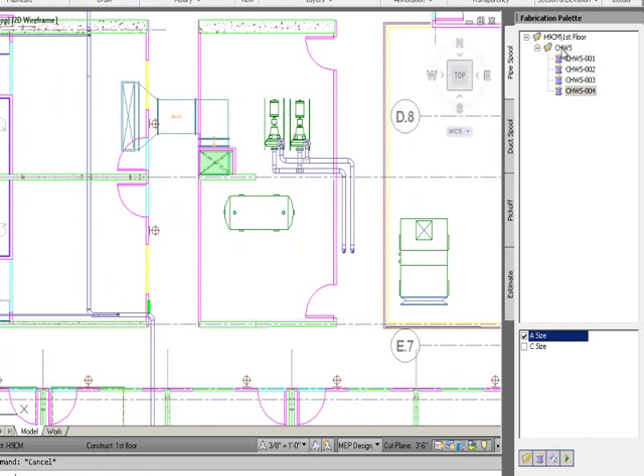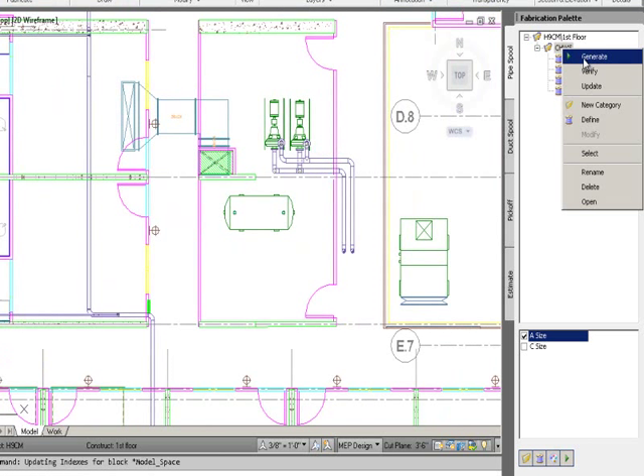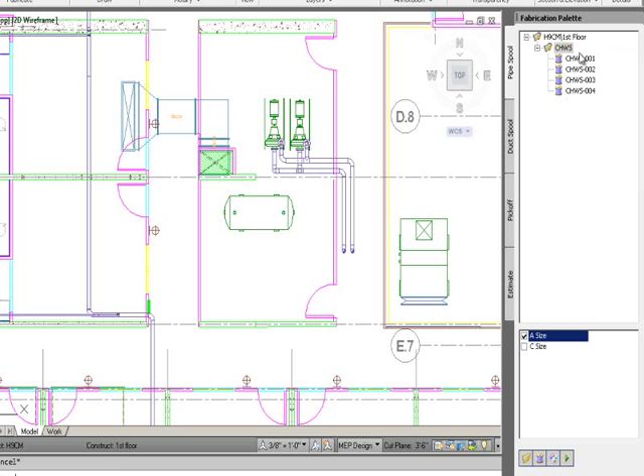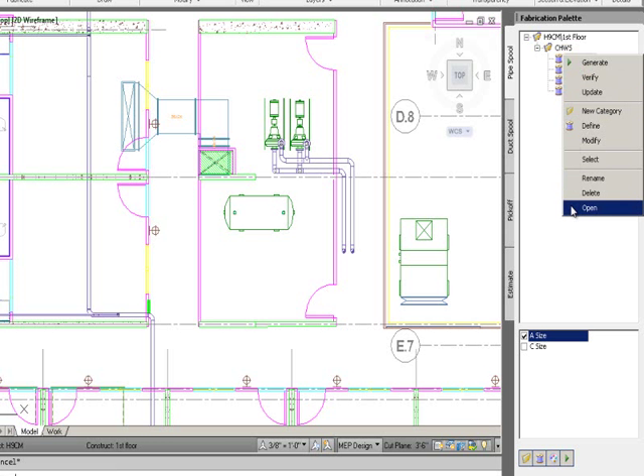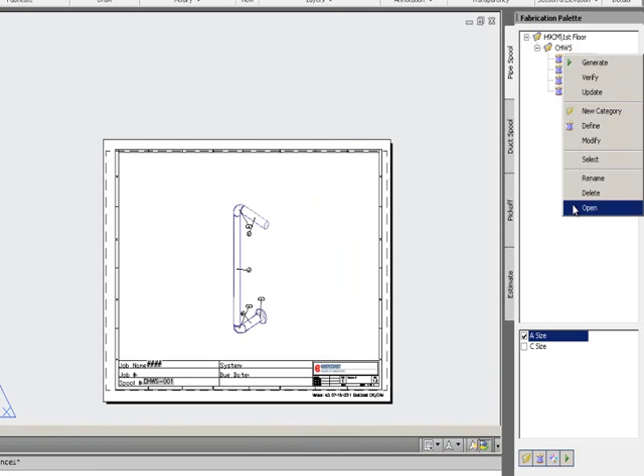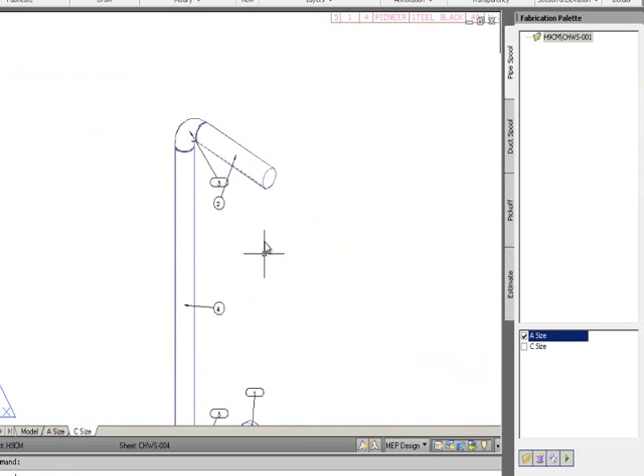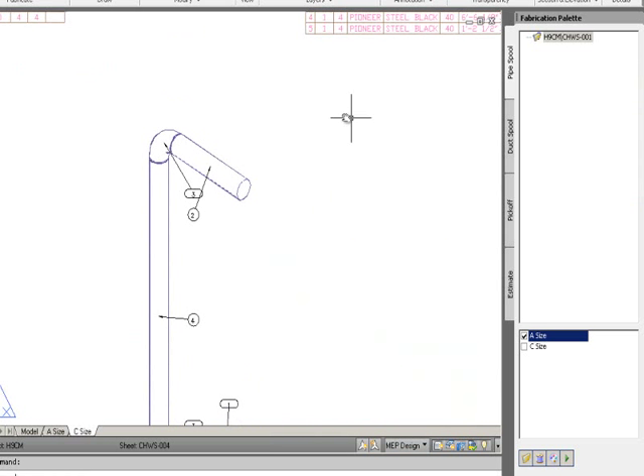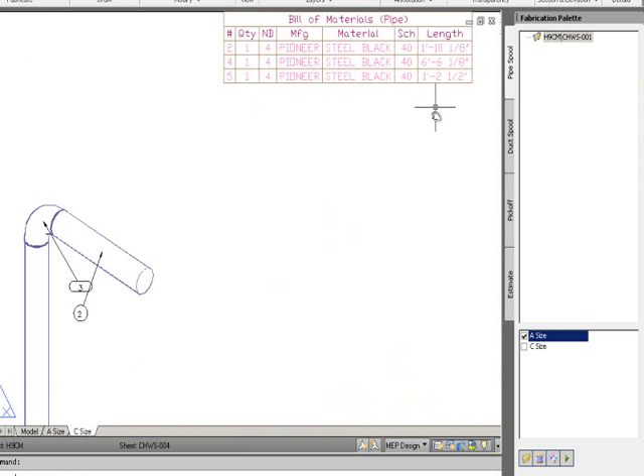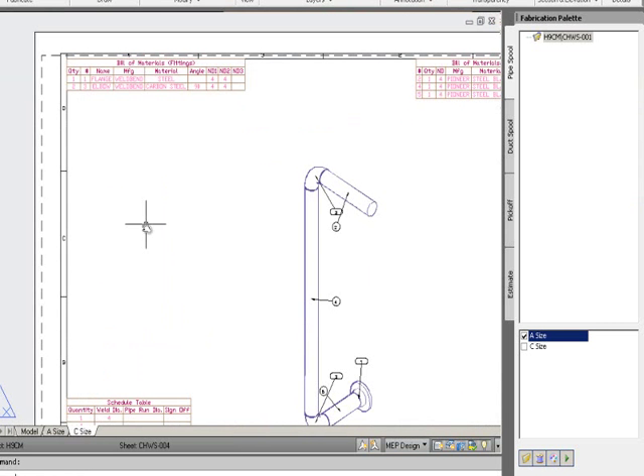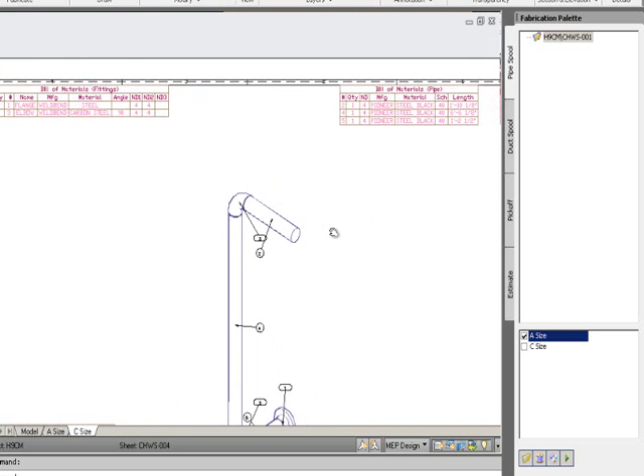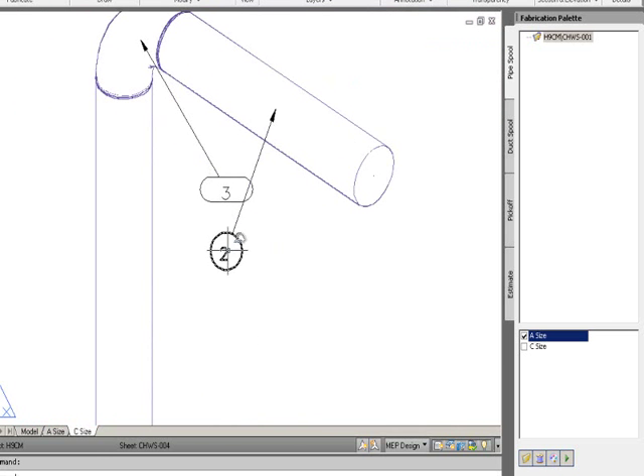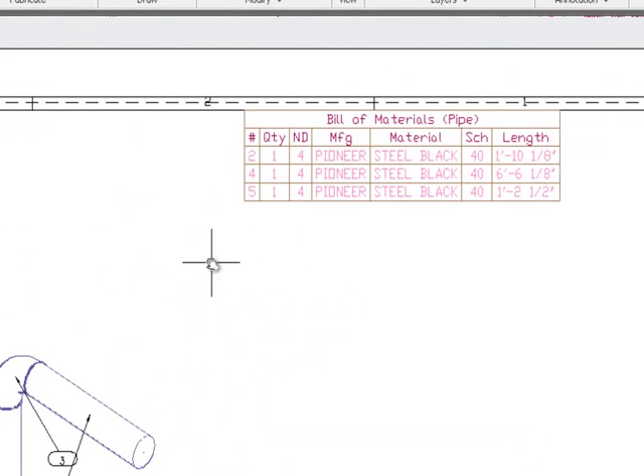From there I generate those four spools, letting the system create a spool drawing for each one. Opening the first spool, it's placed into my drawing template file showing part numbers, exact cut lengths of the pipe, and all fittings listed. Looking at part number two, it shows a cut length of one foot ten and one-eighth.